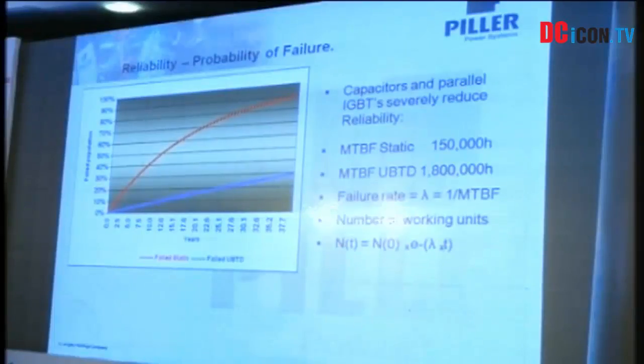Now, after efficiency, we have to look at the reliability, the probability of failure of these UPS. Okay. In a static UPS, what does it consist of? It consists of switching devices called IGBTs. An IGBT switches at 2 kilohertz. 2 kilohertz is a very high frequency of switching. So any particular switch which keeps on operating has a very high possibility of failing. And then capacitors also charge and discharge every time, and due to that, there are a lot of failures of capacitors. And the battery, of course, is charging and discharging.